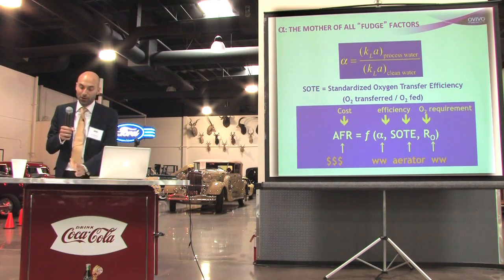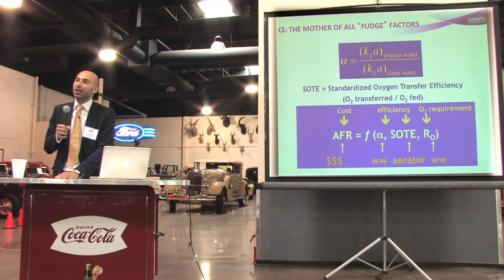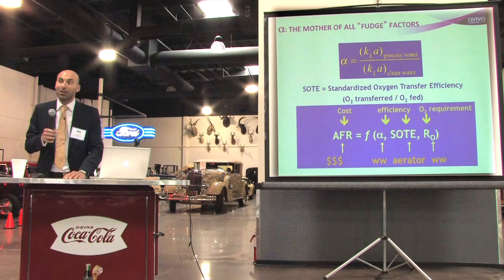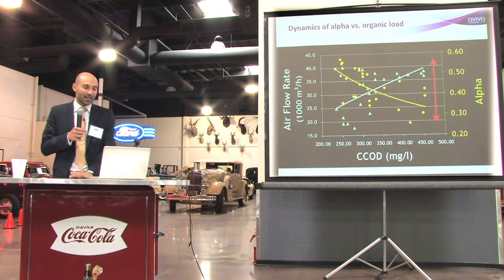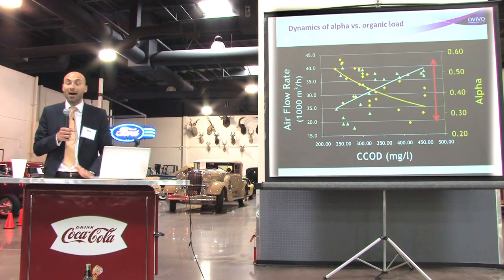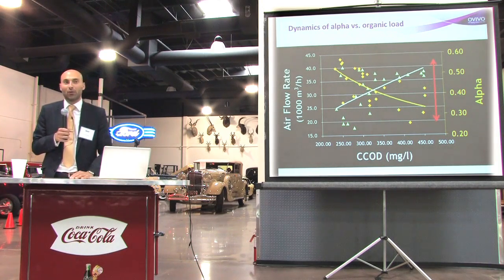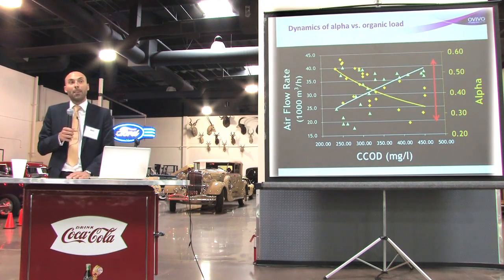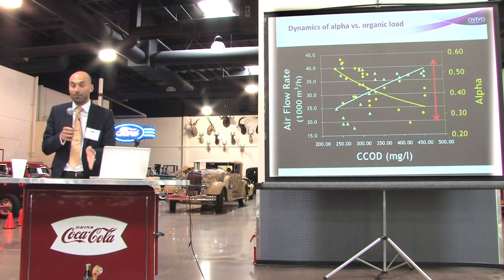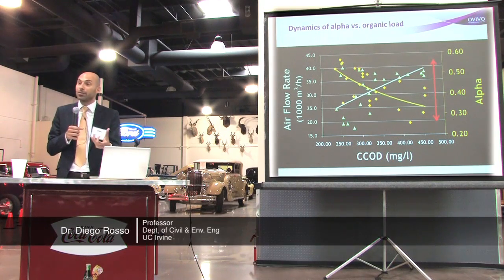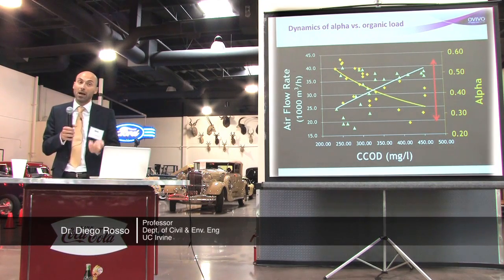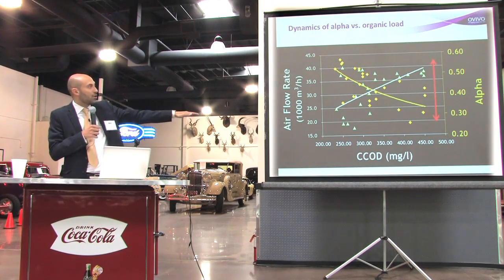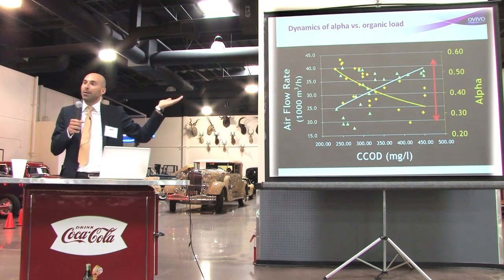In a study Mike and I worked on in Simi Valley, we conducted 24-hour tests measuring alpha·SOTE — we had SOTE values from the manufacturer and measured airflow multiple times per hour, plus grab samples with oxygen demand profiles. This let us create a graph of airflow rate versus COD showing that airflow rate increases when there's more oxygen demand because the controller detects depressed DO and calls for more air.